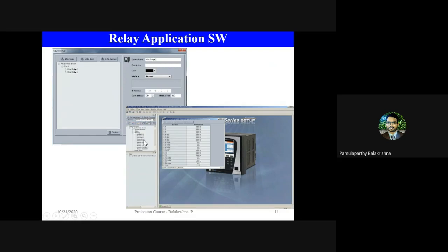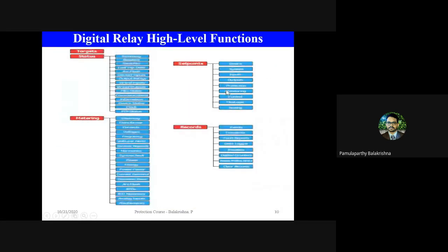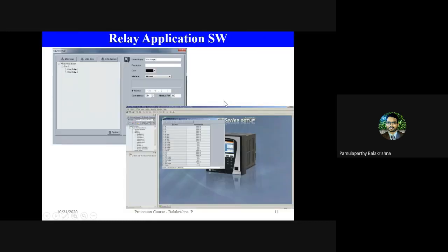And from here itself, you can also configure. So whatever I told you, the set points, the way the protection function has to behave, can also be configured using this relay software. Okay, so this is a one-to-one software, which means at a time you can connect to only one relay and then configure or view waveforms, or do anything that is required to be performed in the field by the operator.